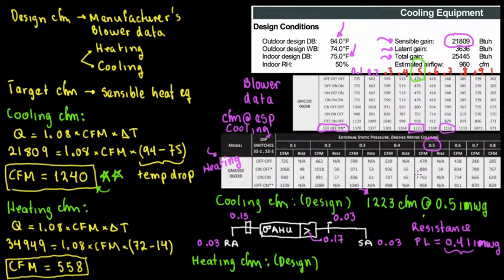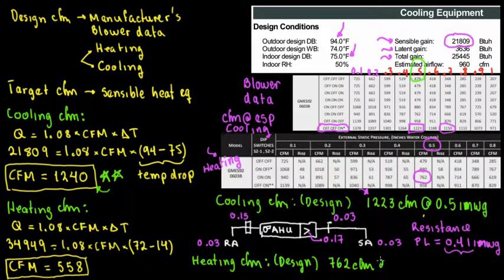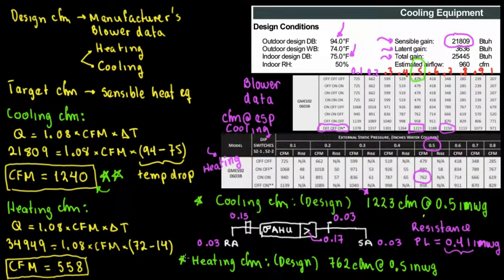The design CFM closest to the target of 558 is 762 CFM at 0.5 inches of water column. So the design heating CFM is 762 CFM at 0.5 inches of water gauge. This is the first step to perform duct design, because after we have the complete CFM, we can distribute the CFM to different ducts.